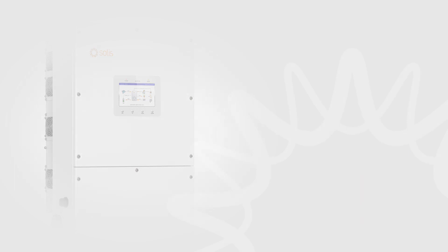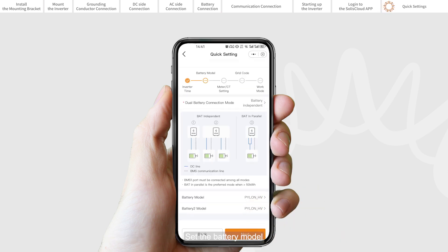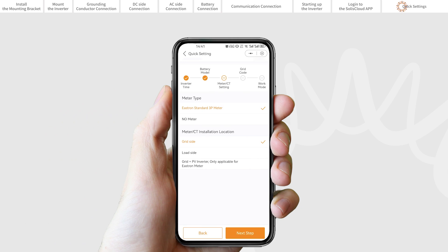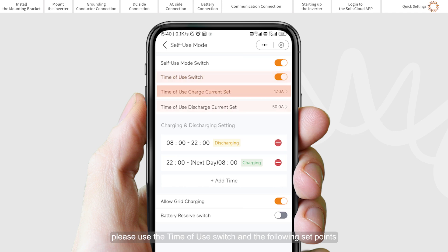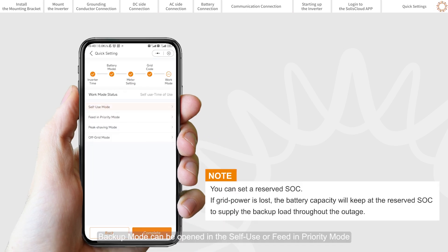Quick settings. You can quickly set the inverter date and time by selecting Follow Phone Time. Set the battery model — if no battery is connected, please select No Battery to avoid alarms. Select whether you will be using CT or an Eastron 3-phase meter. Set the grid code according to the local country standard. Set the work mode — the recommended setting is self-use mode, which maximizes use of PV power generation for commercial electricity or stores it in batteries. To manually control battery charging and discharging with respect to time, use the Time of Use switch and the corresponding set points. Allow Grid Charging is recommended to be turned on. Backup mode can be enabled in self-use or feed-in priority mode.